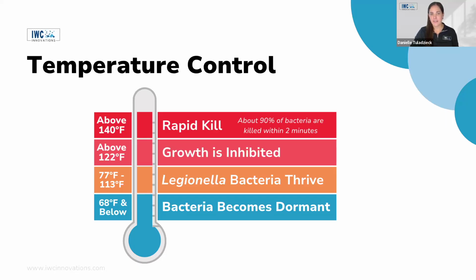As with all things, we have to acknowledge limitations. If you're provided water that might already be in the ideal bacterial growth range, you have no control over this parameter. So we have to focus on other elements to help control. Temperature control is only one tool, not always feasible. It's important to measure, log, and review temperatures regularly. This will allow you to catch issues early on and also understand where you may have seasonal adjustments needed to your water management practices and inform how we can layer protective measures.